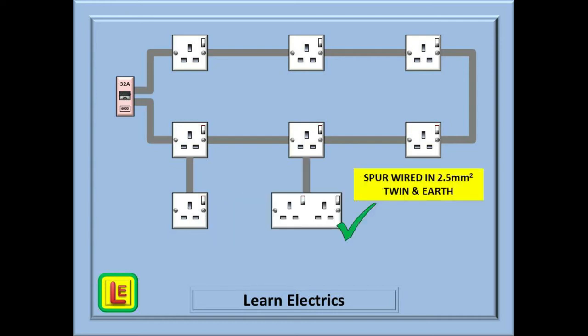We could add a second spur to a different socket. This time it is a double outlet and it is connected by a 2.5mm cable. This is still correct as it is assumed very unlikely that both sockets of a double outlet will each draw maximum current.